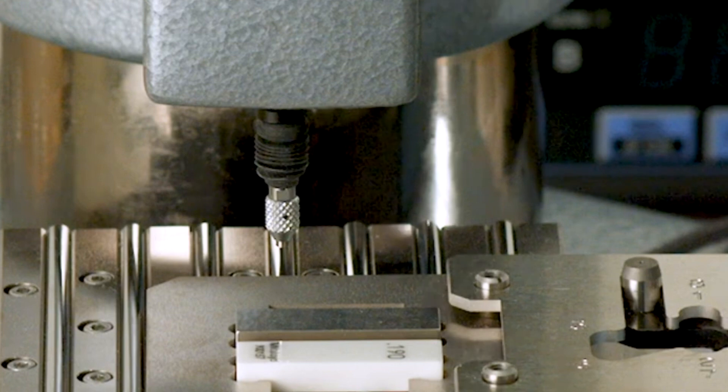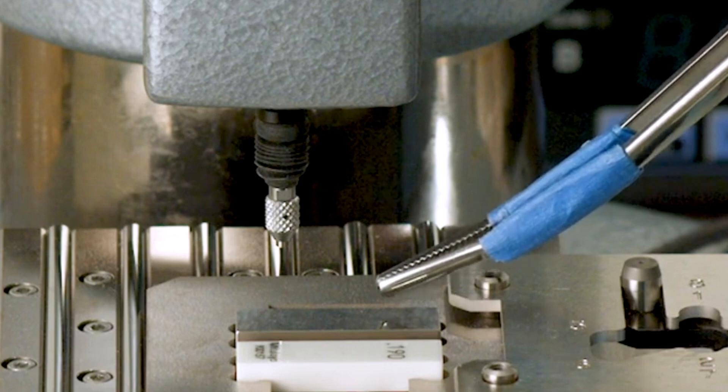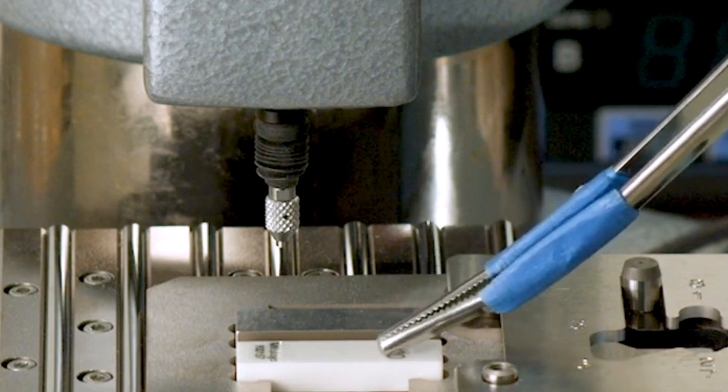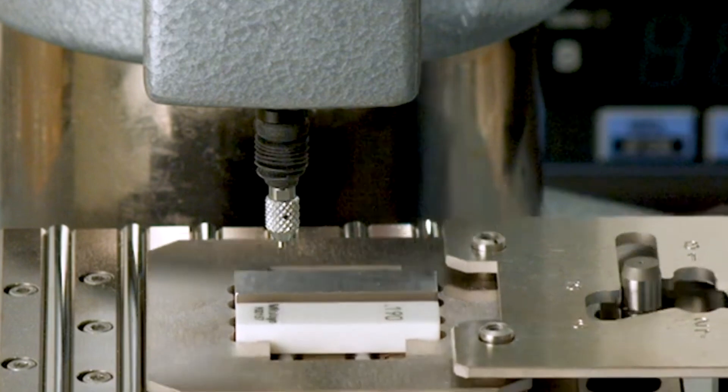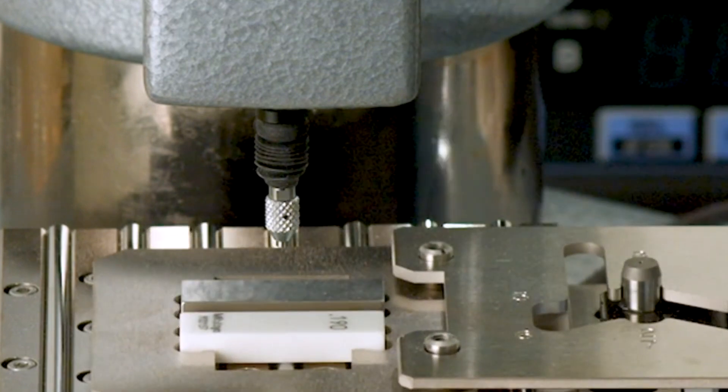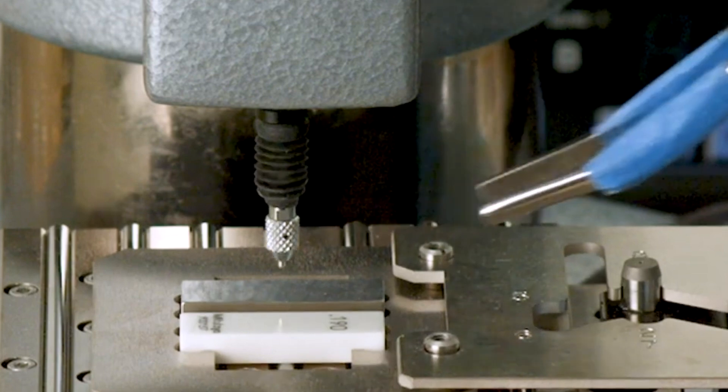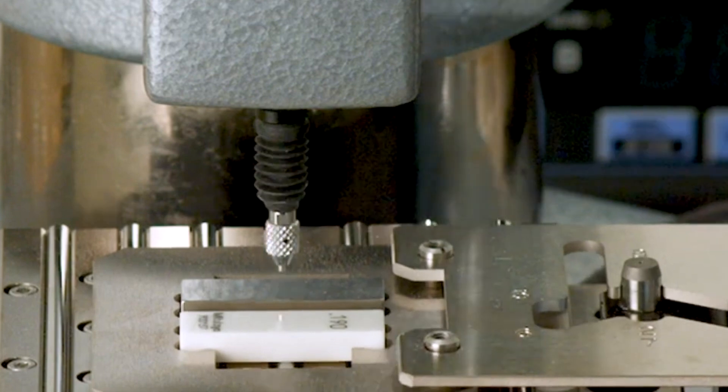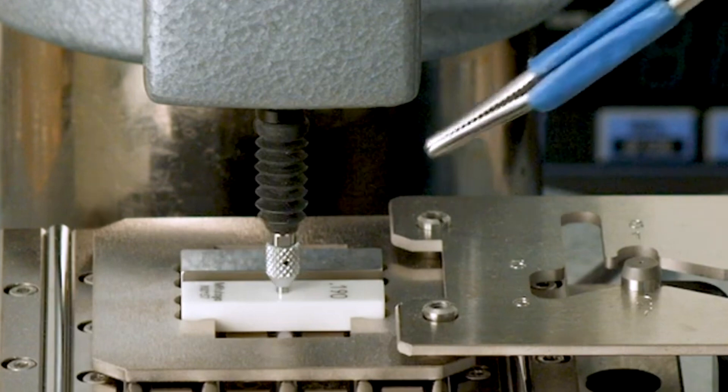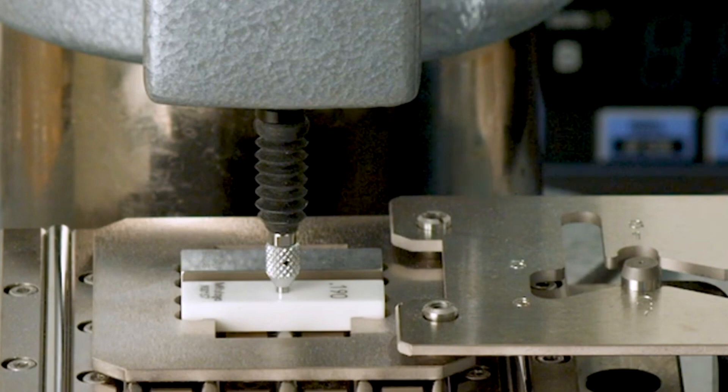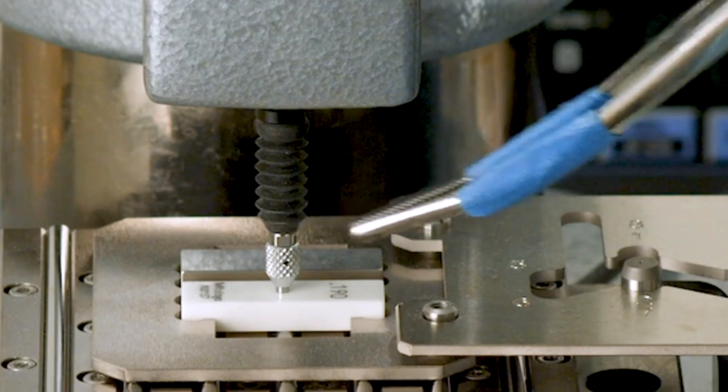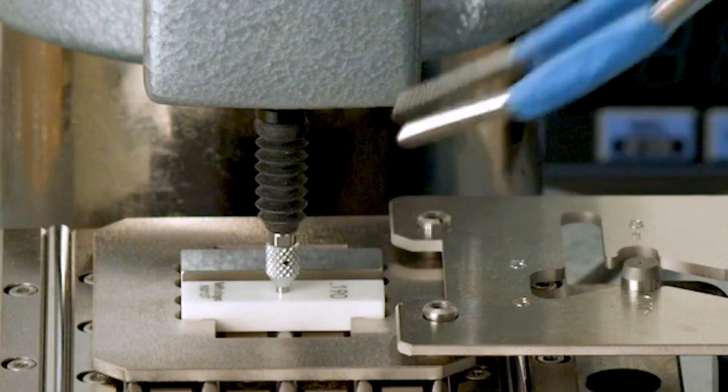Gauge blocks are usually calibrated using a comparison method. This is the master block and this is the customer block to be calibrated. We set the comparator using the master block and then measure the customer block. In accordance to B89.1.9, the length tolerance for gauge blocks applies across the entire surface of the gauge block, not just at that gauge point.